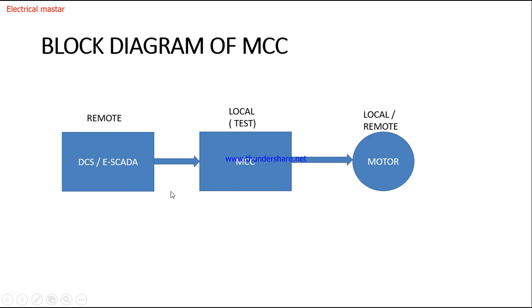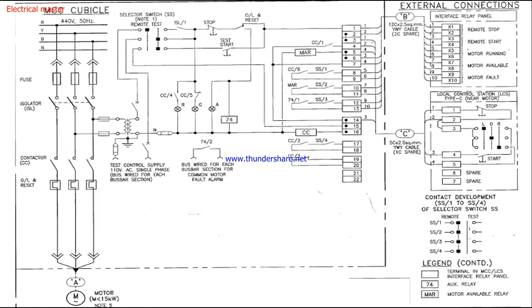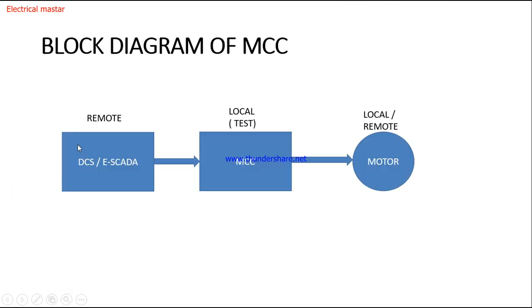Now we will see this drawing and come back to this block diagram, then you will understand the interconnection between the block diagram and the schematic diagram. This is the schematic diagram. First I will explain the power circuit: R, Y, B supply of 440 volt is connected to the control fuse and isolator. When you turn on the isolator, the power supply goes into the magnetic contactor. When the magnetic contactor picks up, it is further transferred to the field motor.